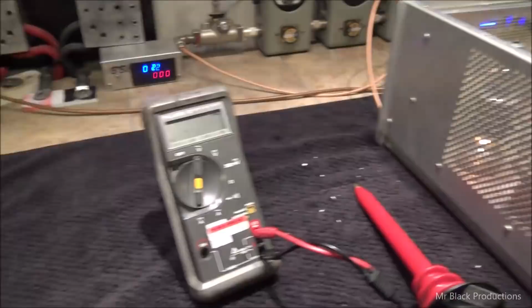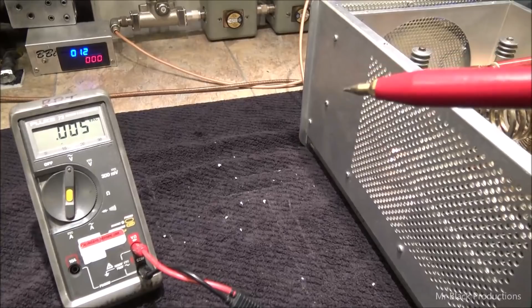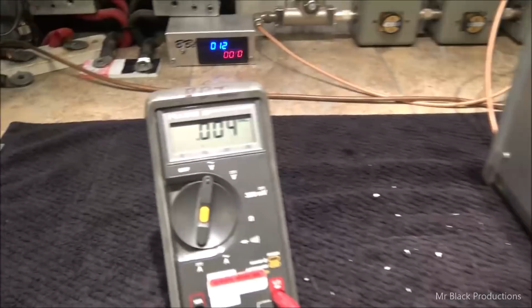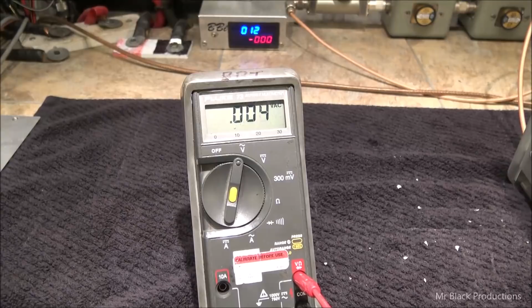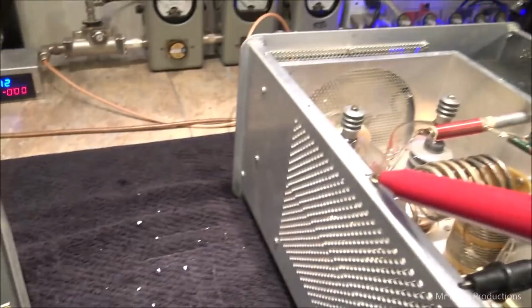But this is the important test. Even though we did a leak down test on those capacitors, we want to double check it on this end. So now we're going to put it to the AC setting. Wait for it to count down. So 0.005, and floating. Now I know that means 0. And why do I know that means 0? It's just the sheer electrical potential in the air. It's 0.005. When we go directly to ground, close the loop up, 0.004, give it a second. 0.005 and floating. See what I'm saying?